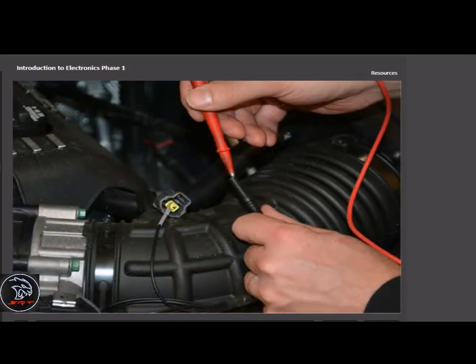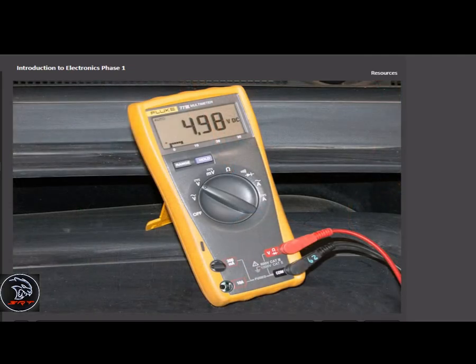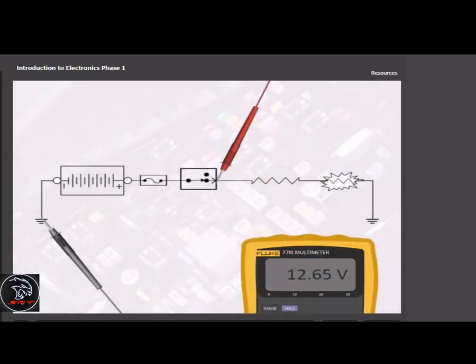To recap, open-circuit voltage testing is limited to verify available voltage and continuity. Closed-circuit testing can easily identify voltage drop caused by unwanted resistance.